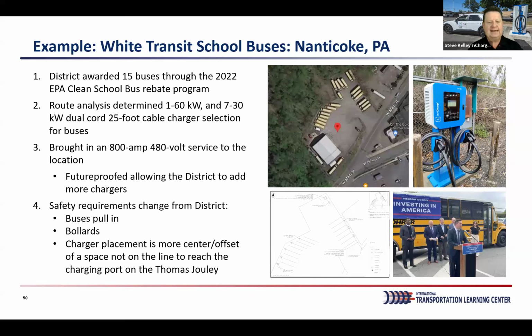In this case we had to install a new 800 amp panel. They had 480 on site already, which was great, so we could go straight DC to DC and add a section for future proofing down the road. They liked that they could still pull in as before, we installed bollards and offset the chargers slightly so even if there was an incident it wouldn't hit the charger. You can see some of the installation pictures here. I think it's a great example of how good design helped them solve critical problems they would have had if we weren't able to get involved and help them understand that.